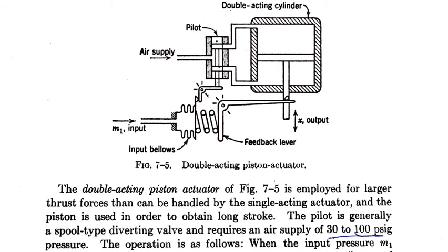So I think this is clear. Whenever the input supply is supplied, the bellow will expand towards the right, that lever will move up, and the air supply coming from the upward direction makes that piston move down, and that stem will also move down. Whenever this moves down, this lever will come down and this will move to the left and come back to the original position. So this is about the fourth type of pneumatic actuator.